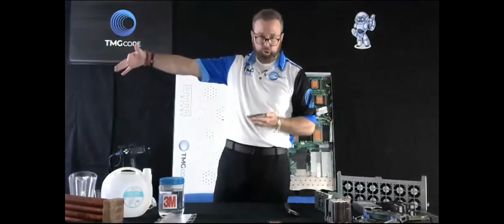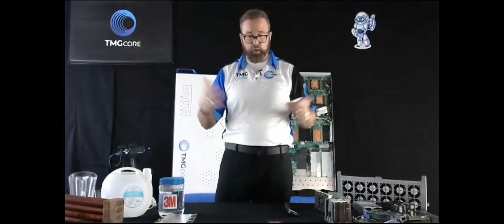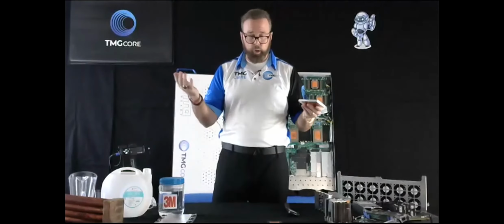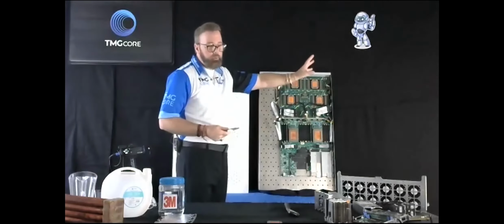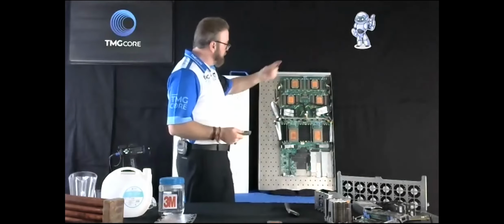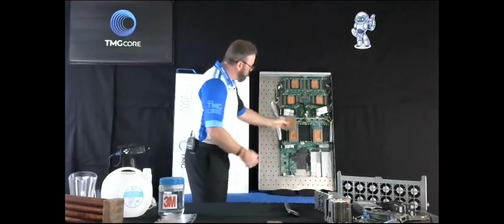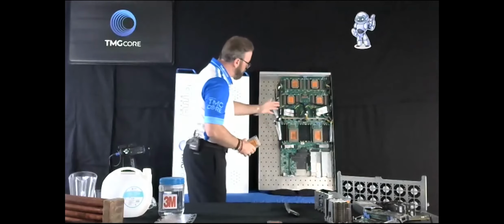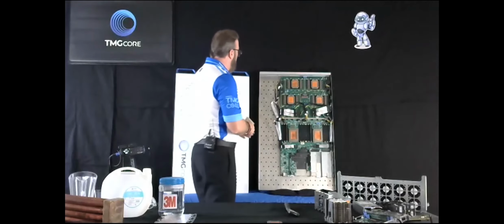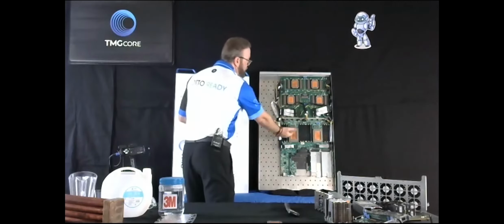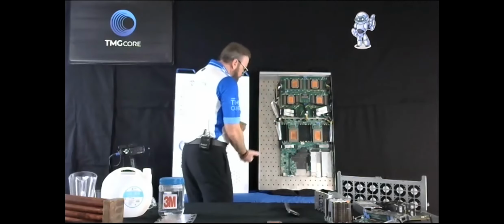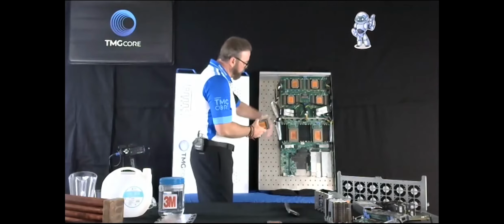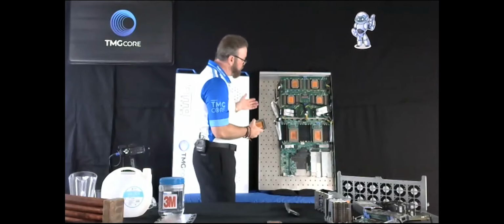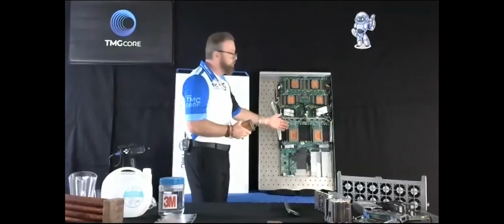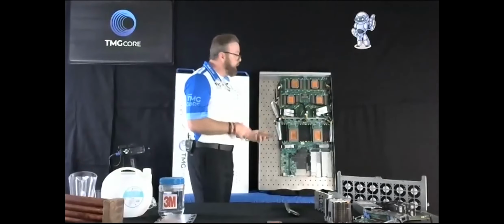You'd have a cool water circulation system. In a large hyperscale deployment with multiple racks, you'd have a secondary system circulating fluid through the cold plate system, with a series of tubes for supply and return. You'd monitor so that as the workload on the chip heats up, circulation increases, or the temperature is modulated to avoid overheating the chips. And it works really well.